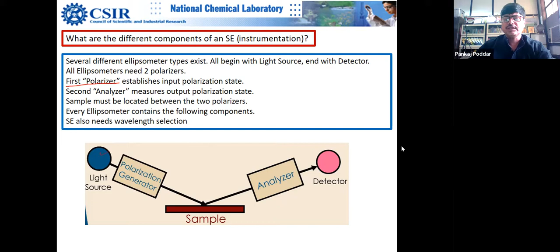In any ellipsometer, first you need a polarizer, then you need an analyzer, then you have a sample, and you have a light source and some kind of detector. That's the basic design. For example, the xenon lamp, I think some students were asking this question. A xenon lamp has a range from 190 nanometer to 2 micrometer, but it's not like you can safely use the entire wavelength range. That's the reason our setup has a limit of 240 nanometer. It can stretch to higher wavelengths further, but below 240, it's very difficult. I think you need a deuterium lamp if you want to go below 240. It can go to 190, but there is a problem.